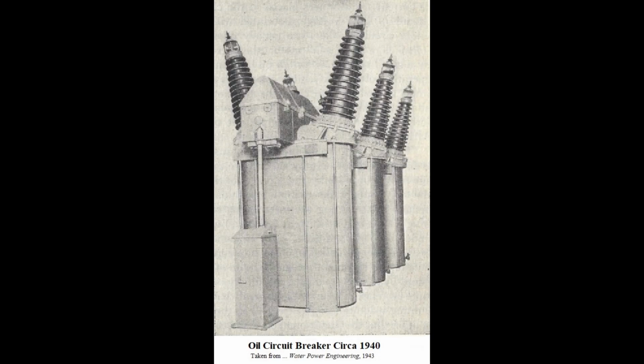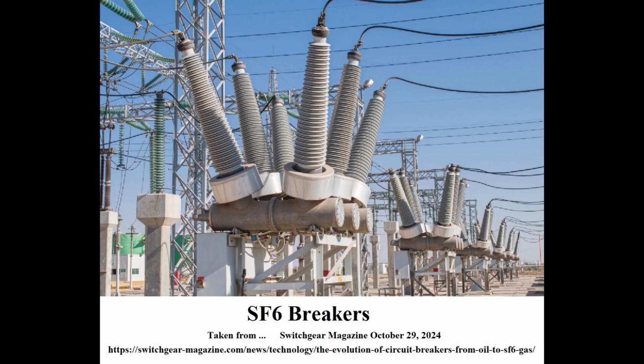Although oil circuit breakers were still being installed in North America during World War II, by the time of the Korean War, around 1950, they were beginning to lose favor. This was due to the obvious hazard of using a flammable liquid to extinguish a plasma-like arc. Sulfur hexafluoride gas breakers are now typically found in high-power applications. SF6 gas has high resistivity, and perhaps more important, it does not support combustion.